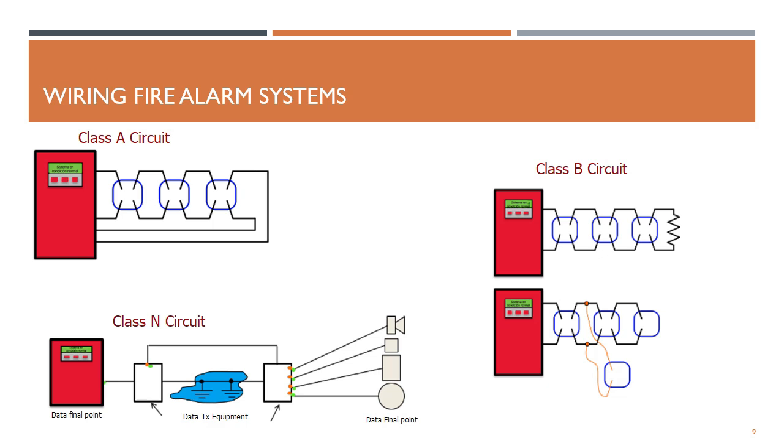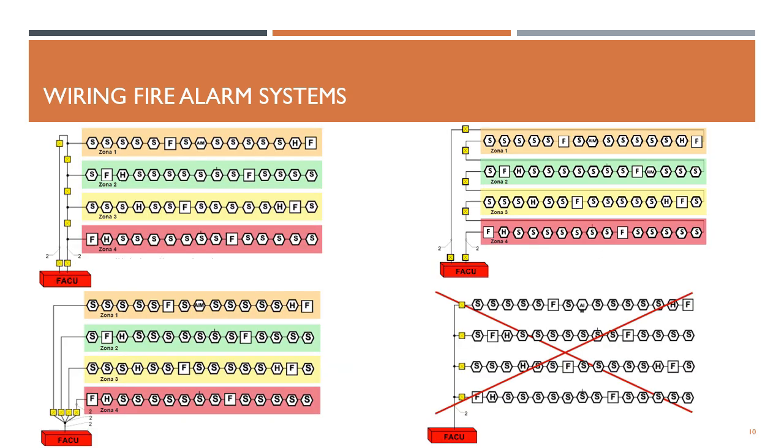Signal transport equipment, whether routers or servers, must be listed for fire alarm service. This is very important. It is not like we can use just any router or server to achieve this kind of communication. Cabling, equipment, and network infrastructure must be clearly separated and identified as a life safety network. For more information, you can find it in the section 23.8.2.6.1 and 12.3.6.